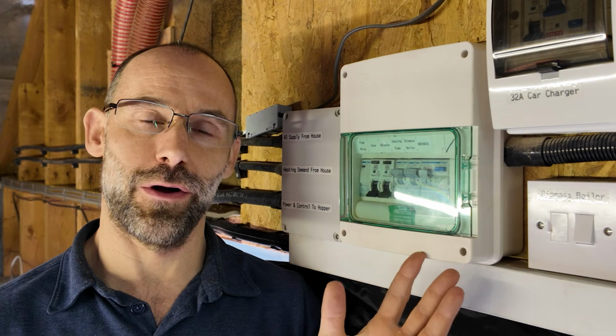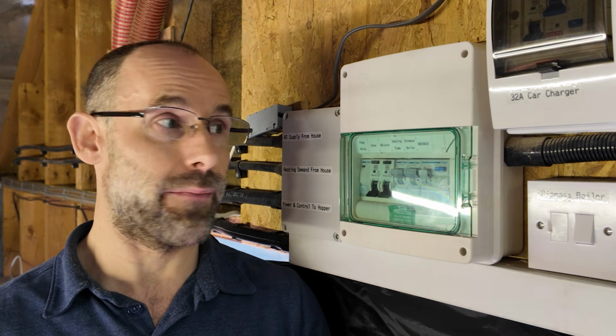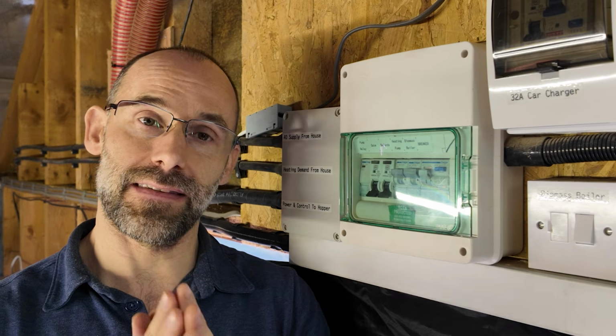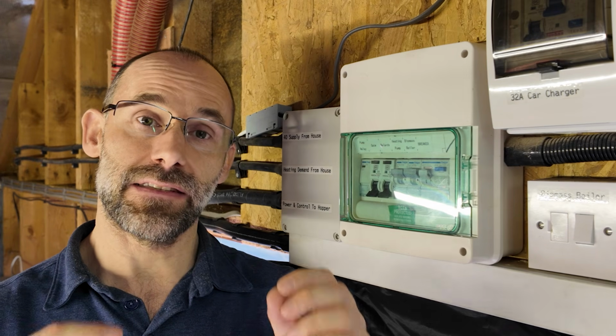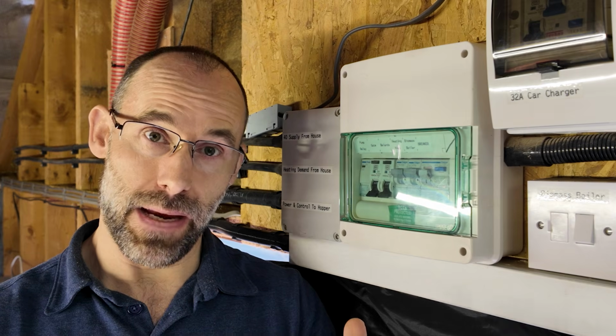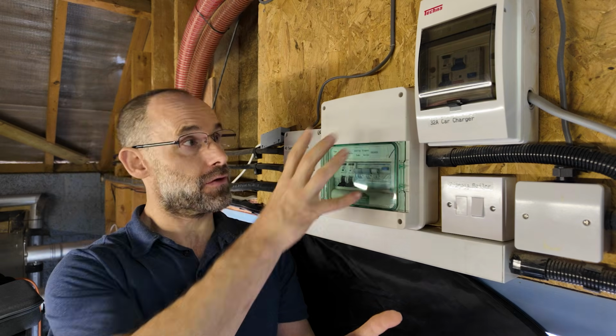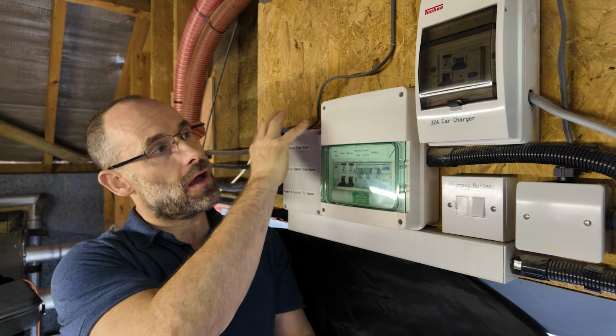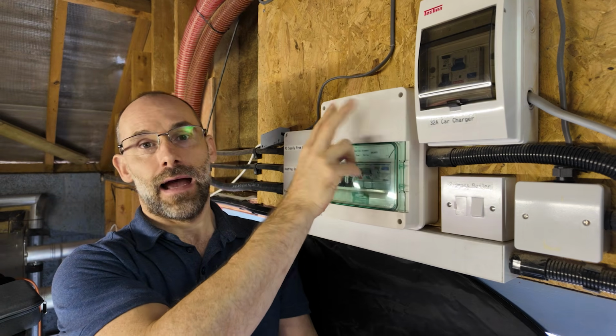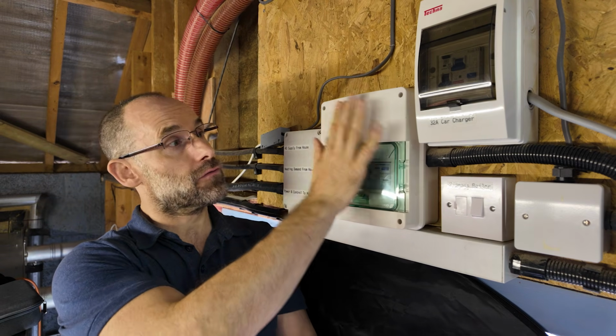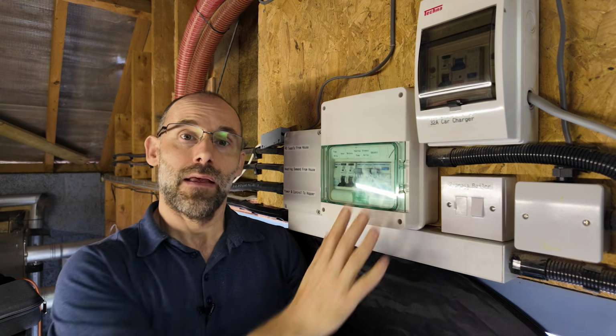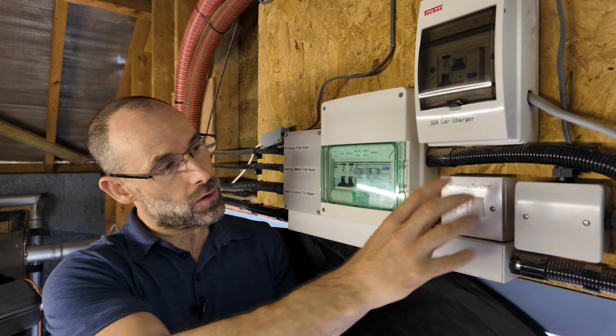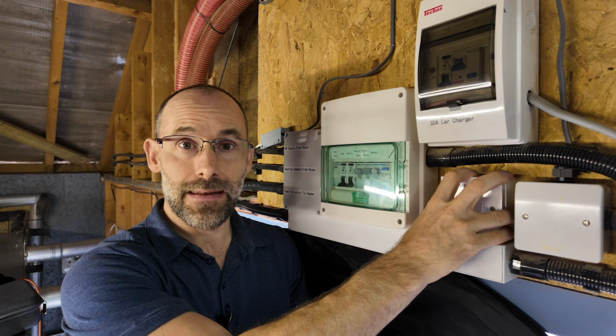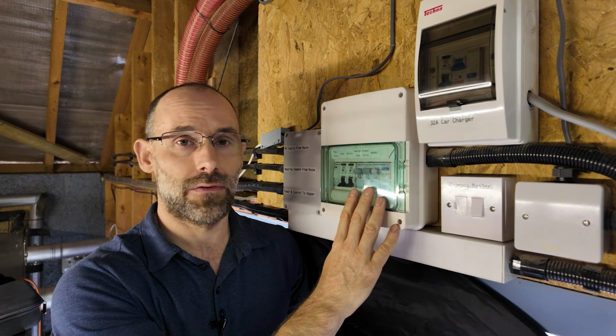Okay, one more test I want to talk about, but I'm not actually going to perform because I know it's not going to work on here with this particular setup and some faults that we have. And that's ZS. That is the system impedance, right? Not just the external. So remember, we measured the resistance of the loop between the line and the CPC to the board. Remember, we did that test. That's all very well, but we also need to know what the circumstance is right down the end here. It's also about making sure that protective device tripping out.